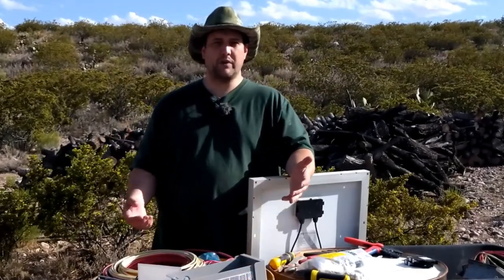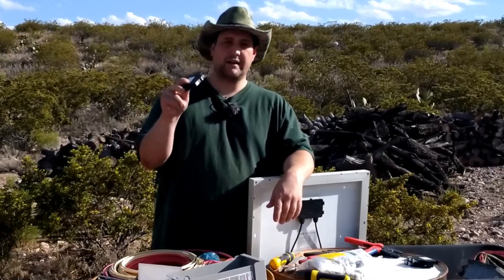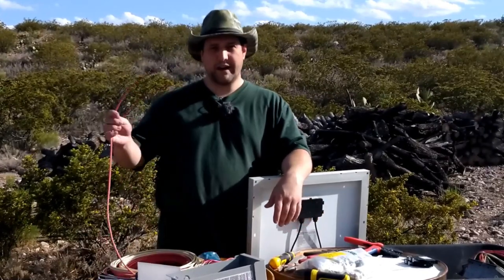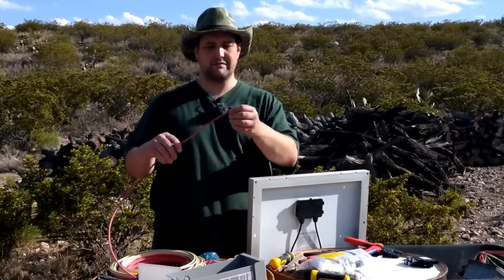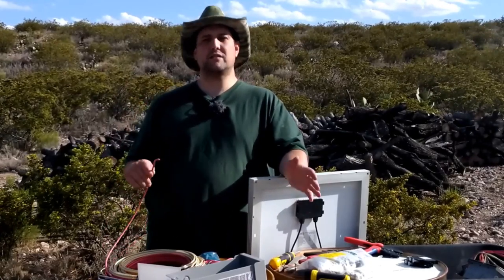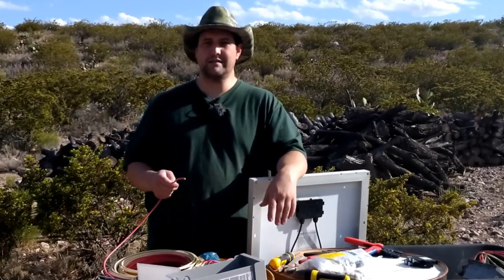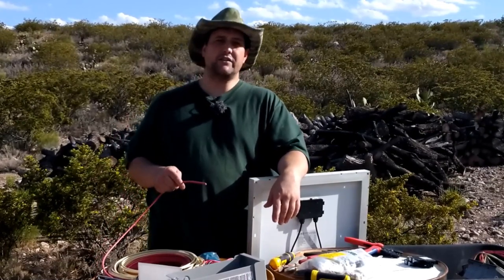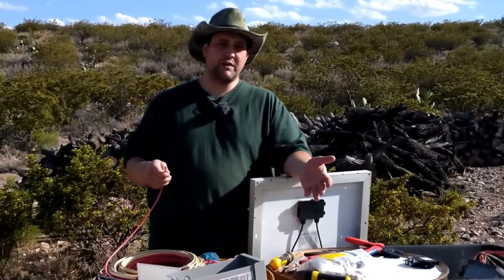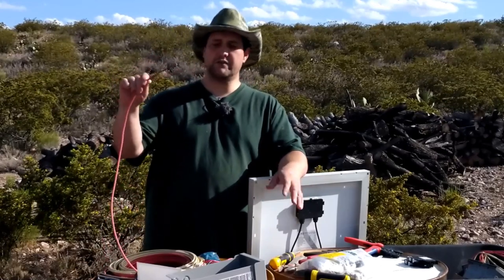In addition to what came in the box from Midnite Solar, we need some additional supplies. We need a breaker — you have to pick these specific to your solar panels. We need wire. This wire is USE-2 rated jacket insulation, which is approved for solar panels. Another approved type is PV wire. The reason you have a limitation on wire type is because it gets really hot and needs to resist UV degradation. They approved two types: USE-2 and PV wire.